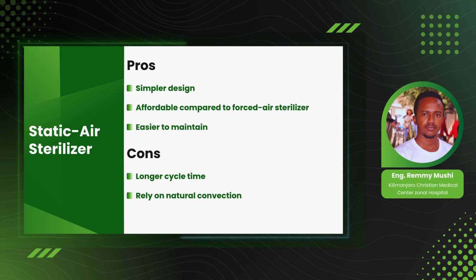Presuming a 6 cubic meter static air sterilizer and a 6 cubic meter forced air dry heat sterilizer, the static sterilizer will have the more affordable price. On the downside, it takes longer to complete the sterilization cycle. This is because it relies on the natural convection of air inside the chamber to ensure that all parts of the load, all parts of the material that you need to be sterile, get there at enough temperature.